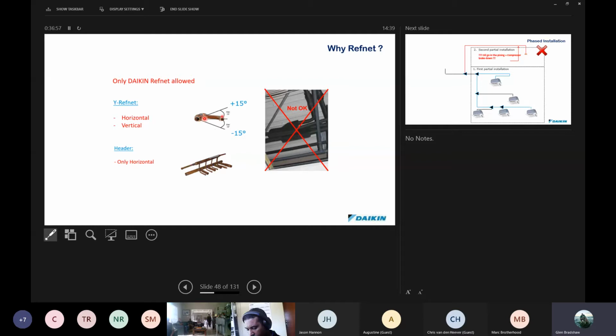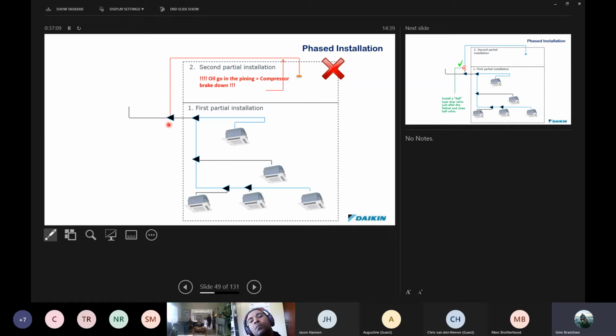And remember that ref nets at the condenser must be mounted horizontal at all times. There's no other way to mount ref nets at the condenser. They must be horizontal. When installing systems, it does happen from time to time that systems are installed in partial first and second phase, or maybe even third phase installations. You may not just extend the piping on the ref net and leave it blanked off. Oil can go into this piping, and there's no way for this oil to make it back to the compressor, and you can damage the compressor.